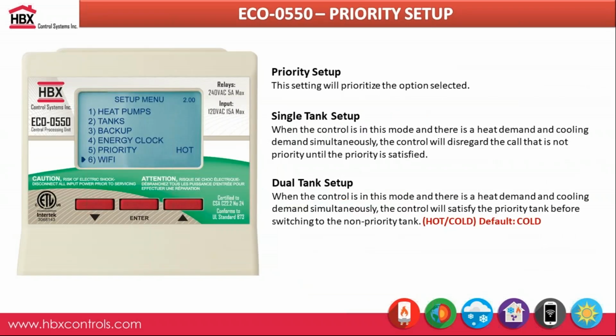In terms of priority setup, if you were to get a heating and cooling demand at the same time, you can put a priority that you always want heating to be over cooling or vice versa. So you do have that option in terms of your priority setup. Again, with our geothermal controllers, we can't do heating and cooling at the same time. It's either we're doing heating, and once it's been satisfied, it'll automatically switch over to cooling if there's a demand. If you did have an application where you wanted to do that, like 4 pipe systems, you would need to get 2 separate Eco 550 controllers, and we do it that way in terms of the setup for those 4 pipe options.